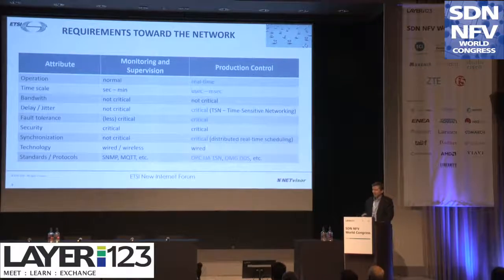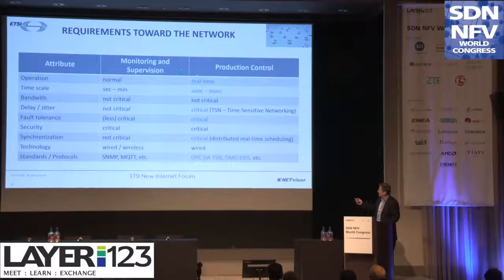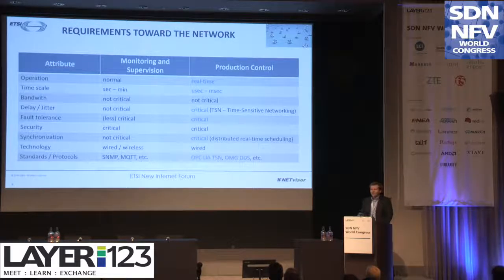On the other hand, if we want to implement a production control system, these requirements are more challenging because the operation is real-time, not normal. The time scale is rather in the microsecond to millisecond frame. The bandwidth is not critical, but the delay jitter, fault tolerance, security, and synchronization are critical factors here. The technology used is almost exclusively wired at the moment.